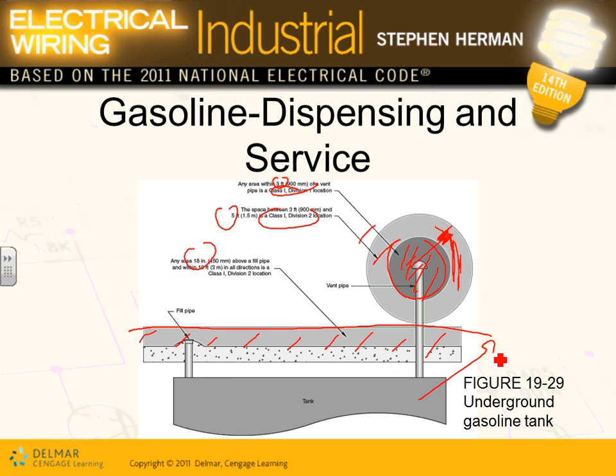Inside the tank is a class 1 div 1. You can't put anything inside the tank other than an intrinsically safe system. That's an underground tank. Does that make sense, guys? So knowing that, can you see that 18 inches right above? When you put in a system, avoid putting anything above the area because it has to be rigid, threaded, expensive.